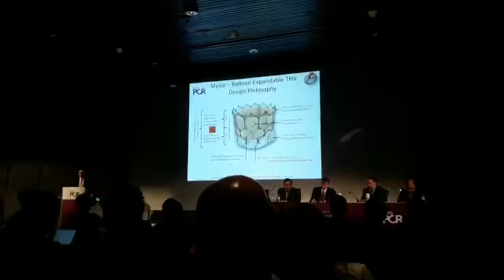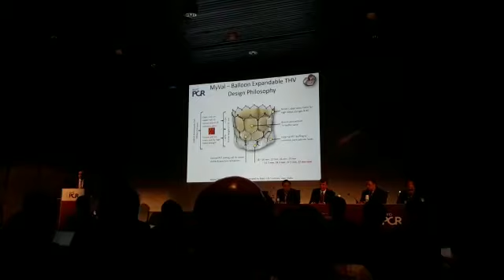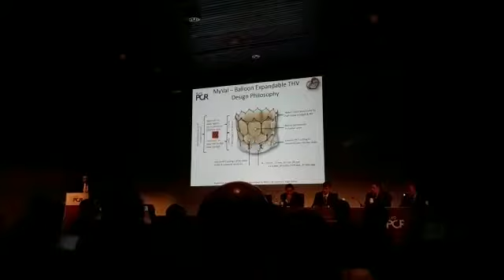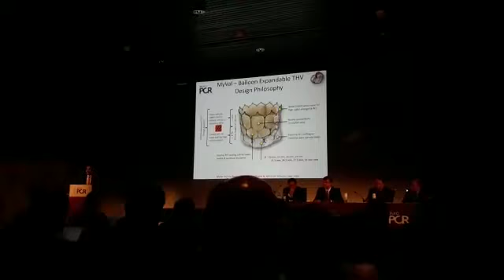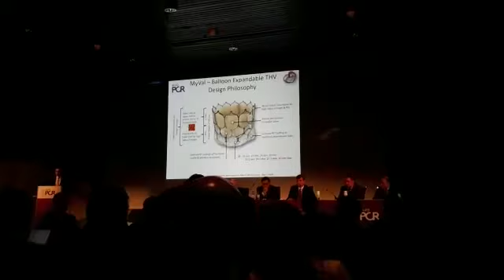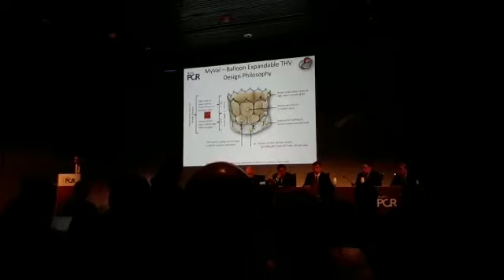MyVal is a novel balloon expandable transcatheter heart valve with a novel hybrid honeycomb cell design concept. 47% of the lower expanded valve frame has closed cells which provide high radial strength. The upper 53% of the expanded valve frame has open cells to ensure easy access to the coronary ostia. The frame is made of nickel cobalt alloy, which provides high radial strength and good radiopacity.